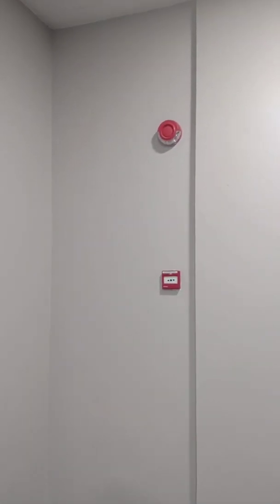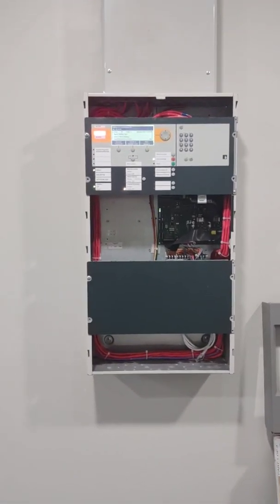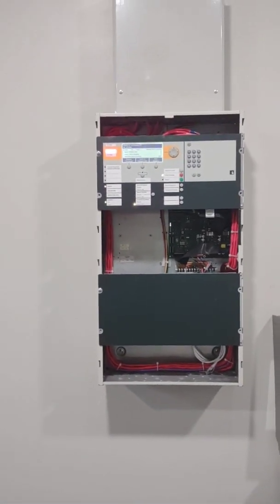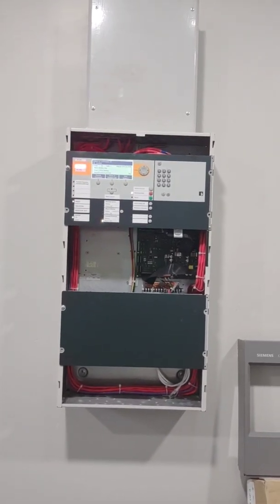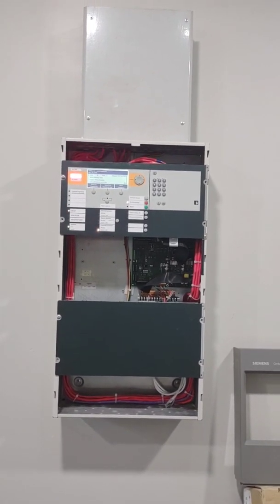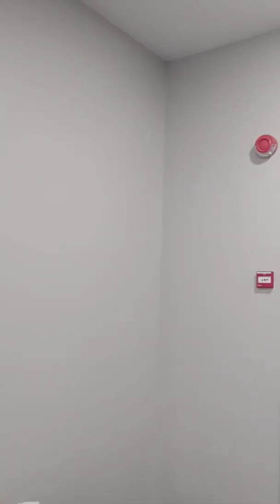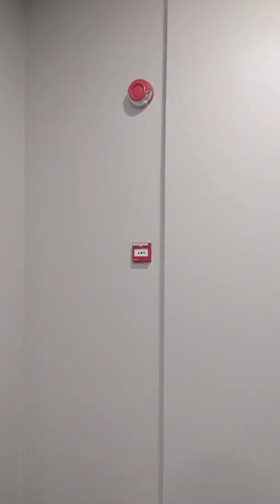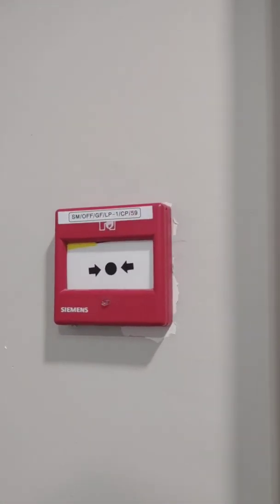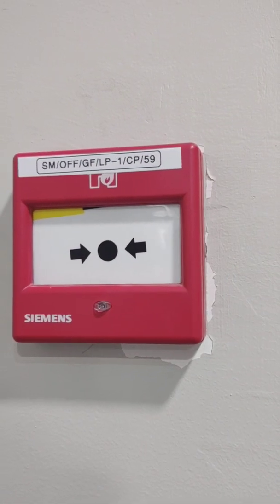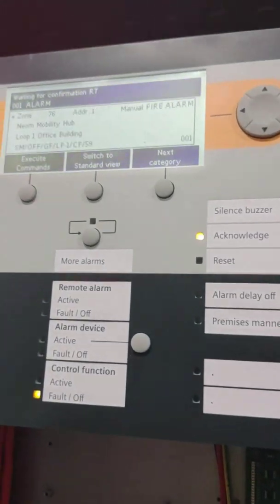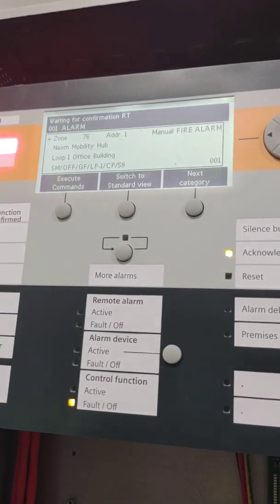So wait until 2 minutes and we can see the alarm — the strobe light will be on and the bell will be on. For the manual call point, you can see the yellow at the top side tab. This is an indication that someone pushed the call point.